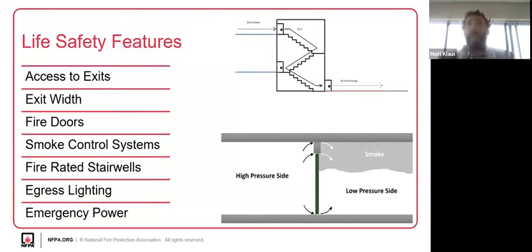It's a partially passive and partially active system. Someone at some point sized those doors and stairwells. Those are passive, they exist, and it's our job to maintain them free and clear. But we also have active components to our egress system, like a smoke control system, emergency lighting, or egress lighting that gets us from the fire area to a safe place. So we've got to maintain that egress path free and clear while relying on those active systems that assist in life safety and egress.